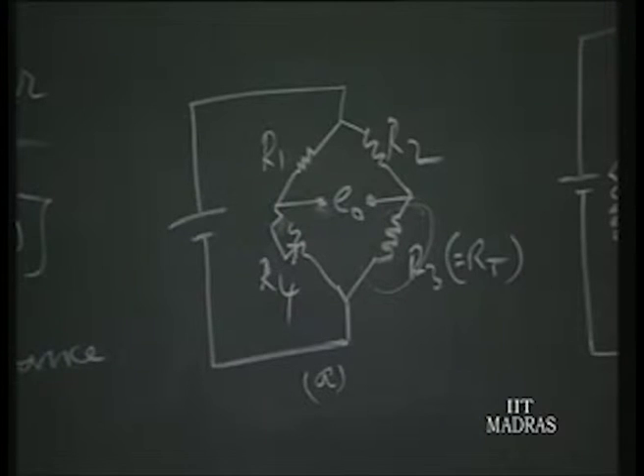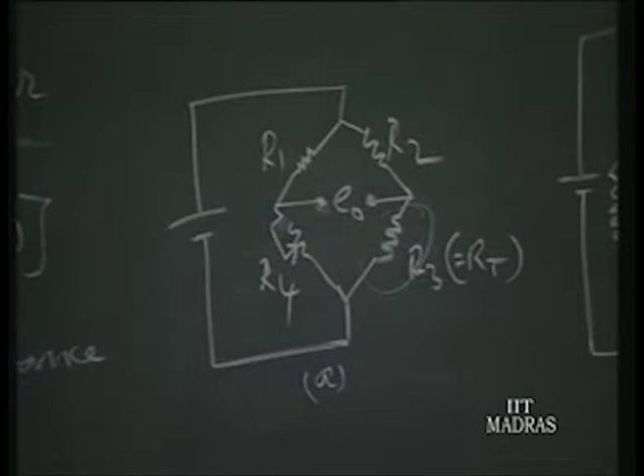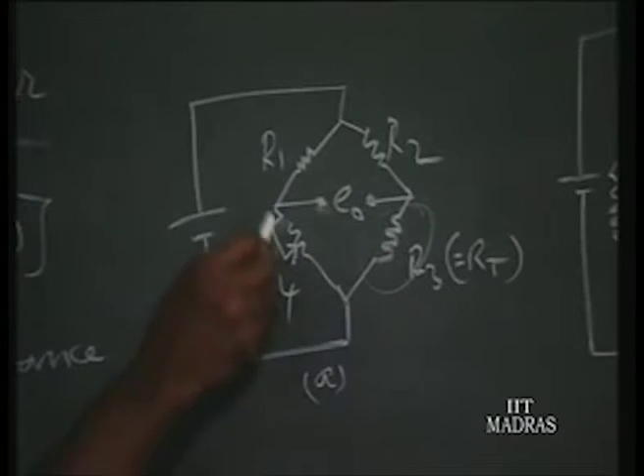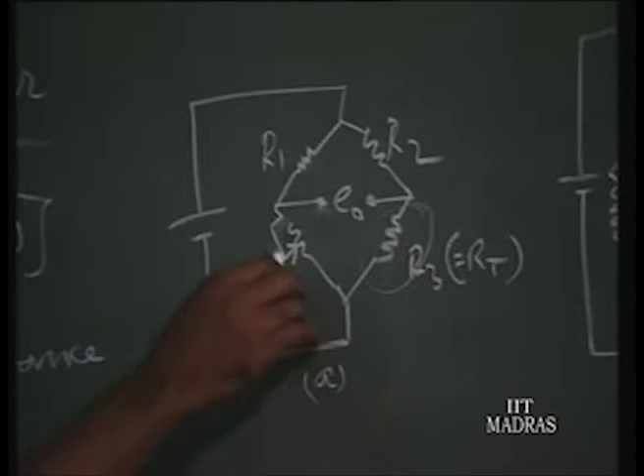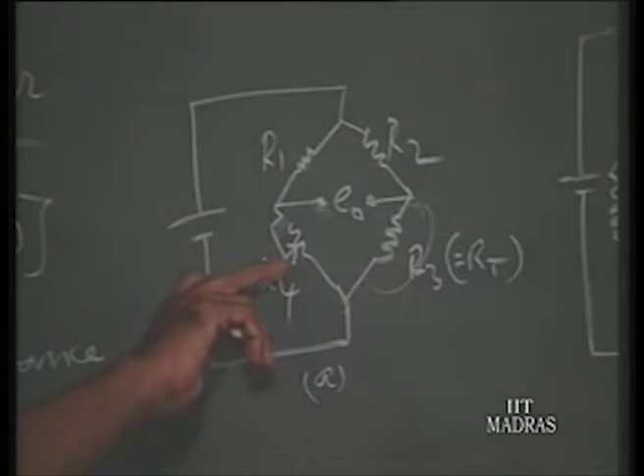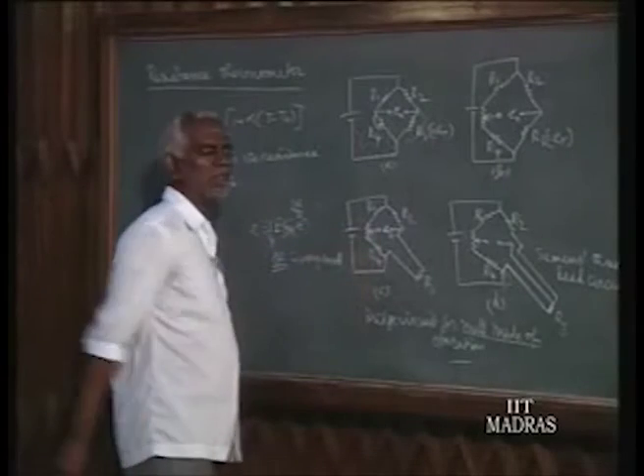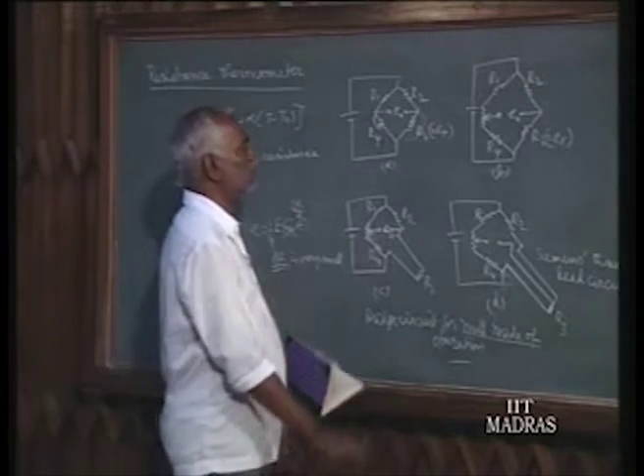The drawback in this null mode of operation is that when we change this resistance, the wiper or contact point is moving over the resistance coil. When it moves at different positions of the coil, it may have different contact resistance. That will form part of R4, the 4th arm of the Wheatstone bridge. Any changing contact resistance will be included, which is not due to the temperature change in R3. So that contact resistance will be an error source for this type of instrumentation.